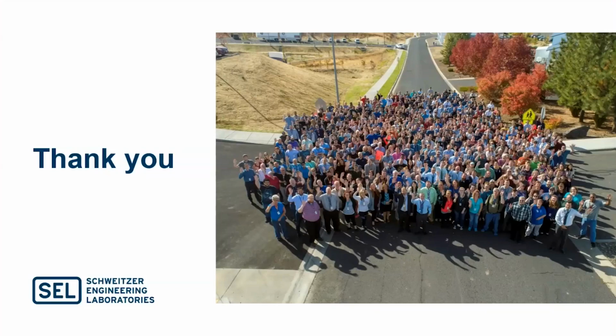Excellent, thank you. We've had a couple of questions talking about integrating PowerMax with systems that have multiple types of assets. Diesel, synchronous generators, inverter-based generators, PV, things like that. How does PowerMax work in an environment of varied assets? Yeah, we are experts at that, and that has taken decades not only to build the skill set of our people, but the algorithms in our products. We put a protective SEL 700G relay, my preferred choice, on most inverters, and I say most because not every inverter may need it, but the batteries almost always do.